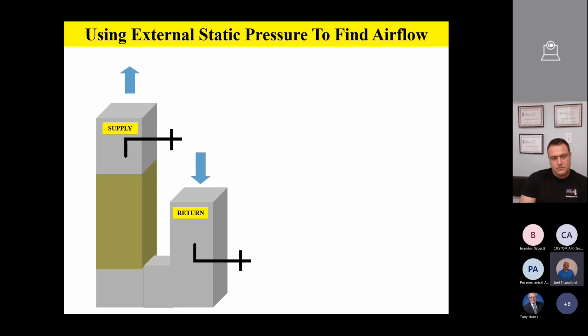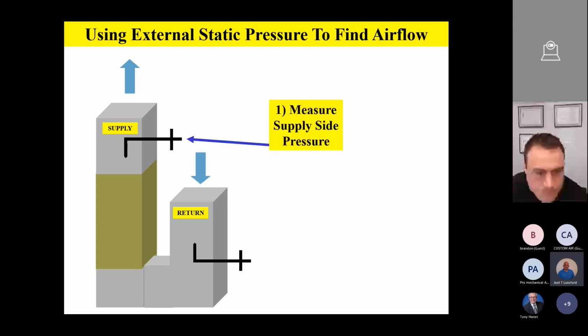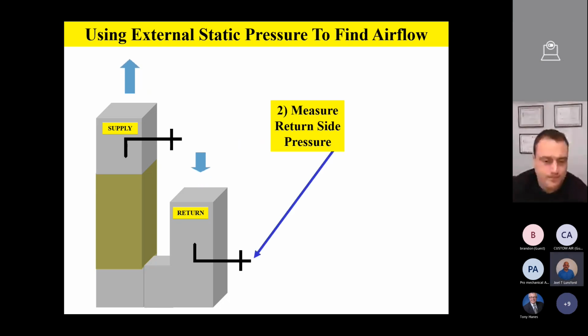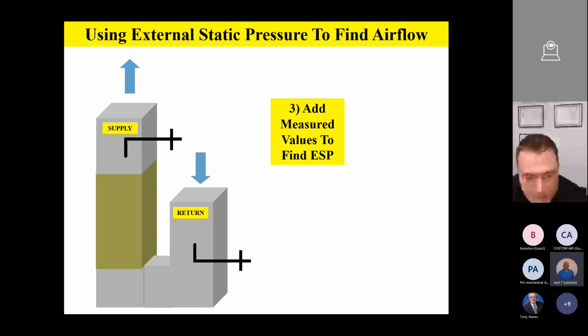Now, let me stress one more time, if the filter's right next to the air handler, be sure and take pressures on both sides. That way you can get a really good idea of what kind of pressure drop you have across that filter. So basically what we're going to do, fellas, we're going to measure our supply side static pressure, step number 1. And then step number 2, we're going to measure our return side pressure. And then step number 3, we're going to add those pressures together to find external static pressure.